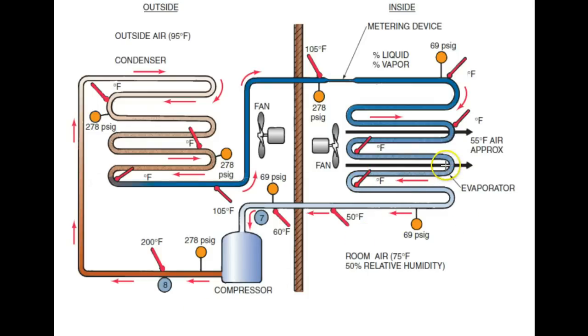Here's one thing that I've noticed. First of all, if you're at this point and you're adding refrigerant and you add a little bit of refrigerant, you're not going to see a huge change in superheat at all. You may not even notice it at all. Then you're going to hit the next point and there may be a subtle change in the superheat and temperatures and pressures. Then you get to this point and it's again incremental and small and you start to wonder what's going on. Now, as you start to approach the point at where it's properly charged and I'm not certain why this is, the temperatures and pressures begin to change much quicker and it's really easy to overshoot your charge because it's been going so slow to begin with.